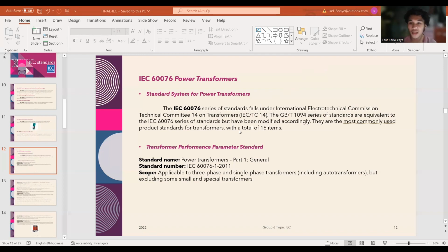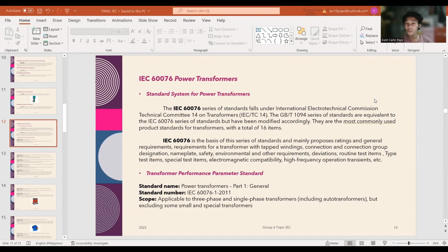This series of standards falls under the International Electrotechnical Commission's Technical Committee 14 on Transformers, IEC TC14. The GB/T 1094 series of standards are equivalent to the IEC 60076 series but have been modified accordingly. Now, the transformer performance parameter standards under IEC 60076. The first part is the general. It is applicable to three-phase and single-phase transformers, including the autotransformer, but excluding some small and special transformers. For those categories of power transformers and reactors which have their own IEC standards, this part is applicable only to the extent to which it is specifically called up by cross-reference in the other standards.